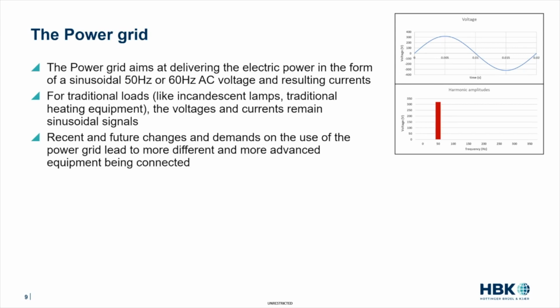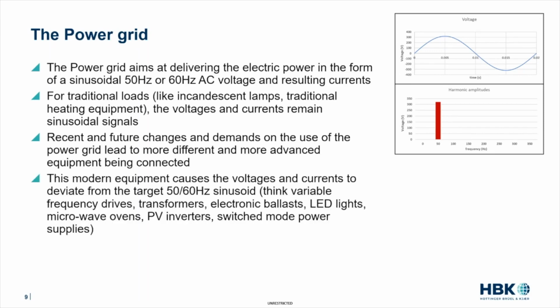But as I mentioned, over the past decades, much more complicated loads are connected to the power grid. You can think, for example, of variable frequency drives, transformers, electronic ballasts, but also LED lights, microwave ovens, photovoltaic inverters, switch mode power supplies, etc. They are no longer very nice linear loads. So if you attach such a device to the power grid, your signals will no longer be sinusoidal. Neither your voltages nor your currents will be sinusoidal.